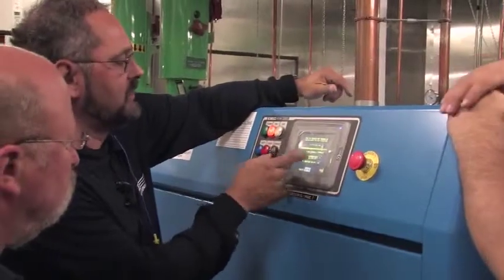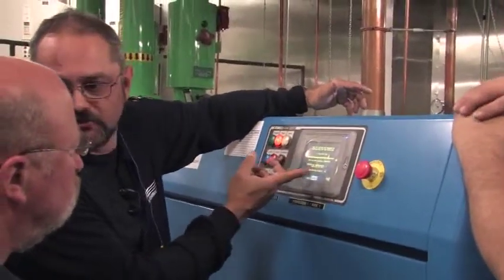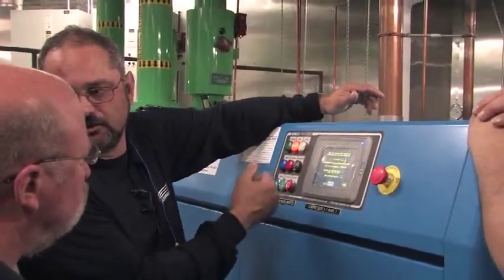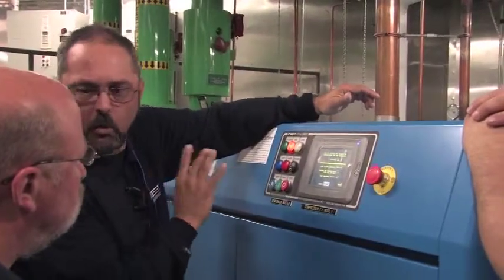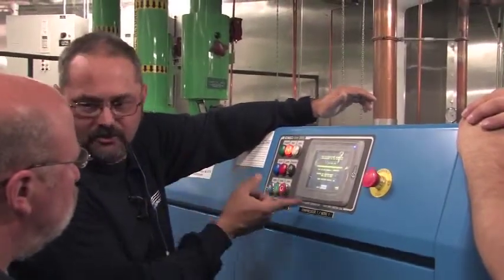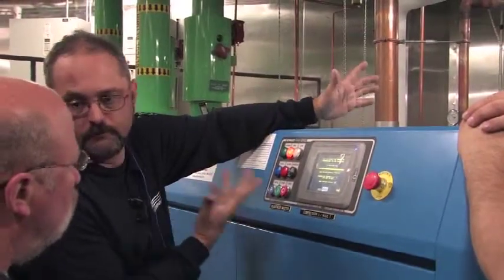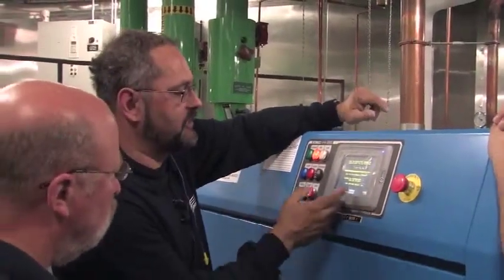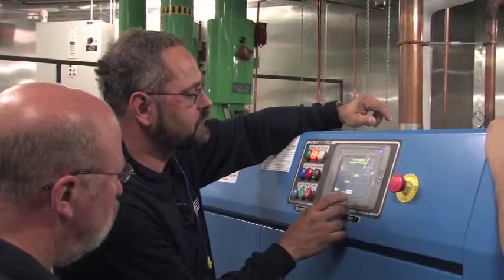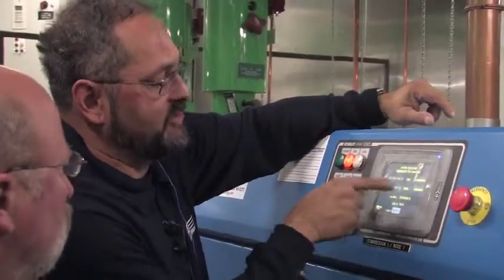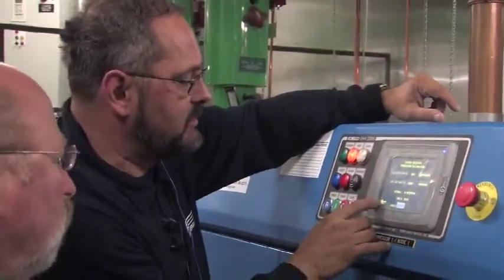Lead/lag turned on, number of compressors for lead/lag. So actually, we could set this so lag and use would trigger. Normally you only need 1, but if you wanted to, you could set the lead/lag on this to trigger at 2. So it's fully configurable, and that's the calibration for that transducer up there.